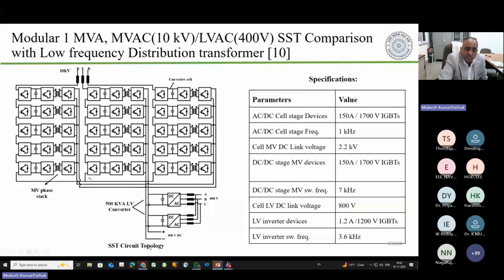Now this LV-DC link is used, in a modular fashion again, with DC to AC modules - first module, second module, and so on. So you can use a number of modules and connect them in parallel to supply the load. You can see what advantage the modularity or modular structure is bringing: here you can connect the desired number of modules as per the load requirement.